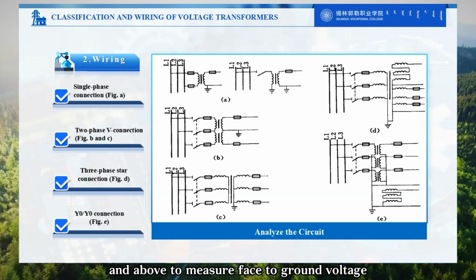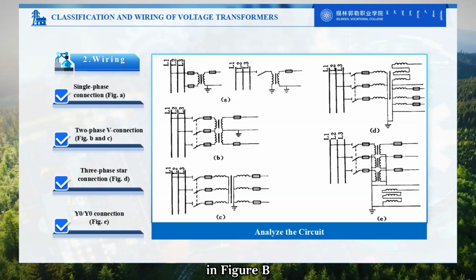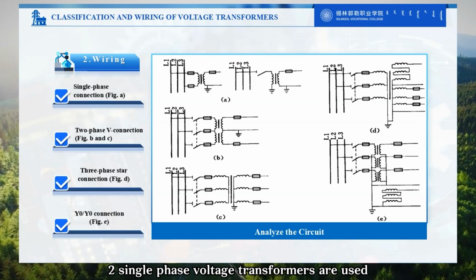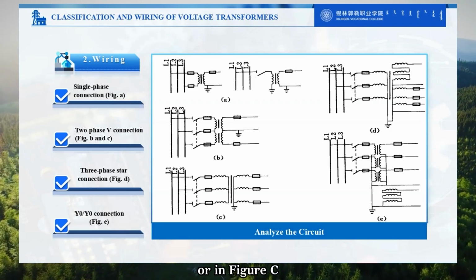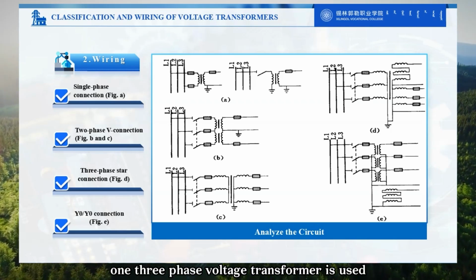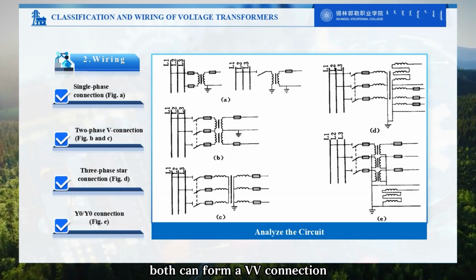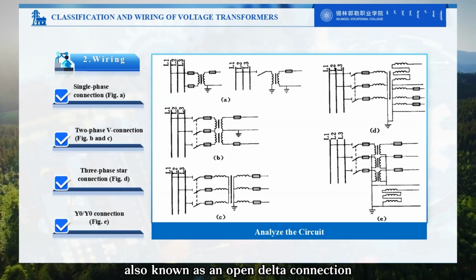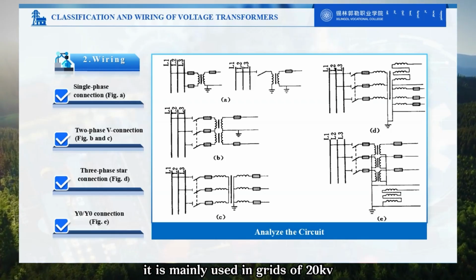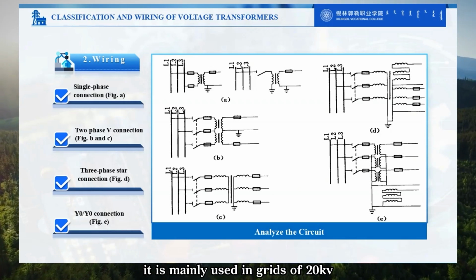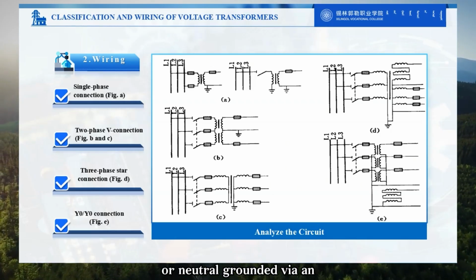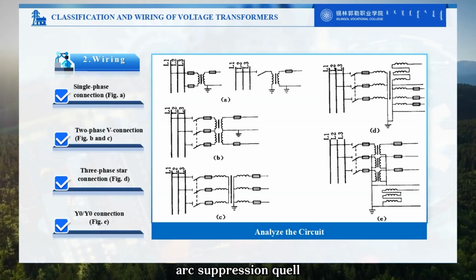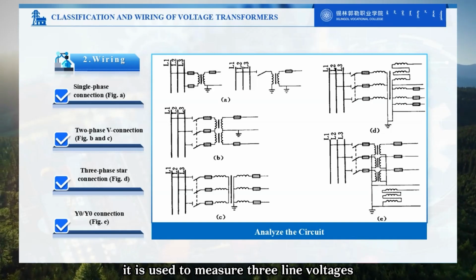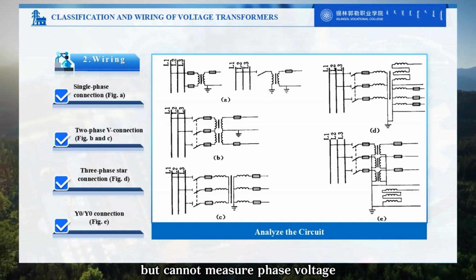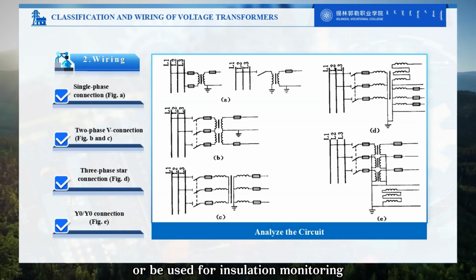to measure phase-to-ground voltage. In Figure B, two single-phase voltage transformers are used, or in Figure C, one three-phase voltage transformer is used. Both can form a VV connection, also known as an open delta connection. It is mainly used in grids of 20 kV and below with ungrounded neutral or neutral grounded via an arc suppression coil. It is used to measure three-line voltages but cannot measure phase voltage or be used for insulation monitoring.